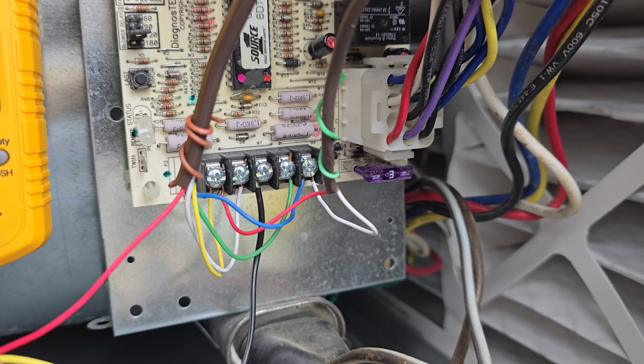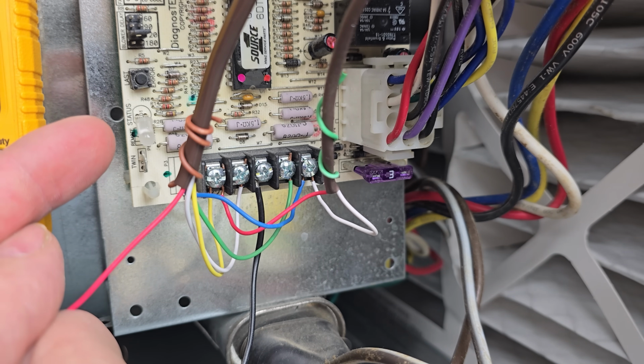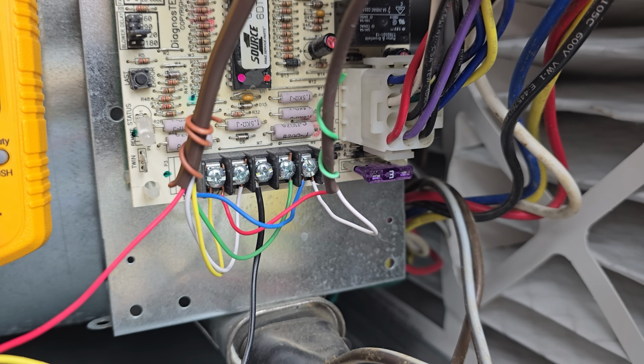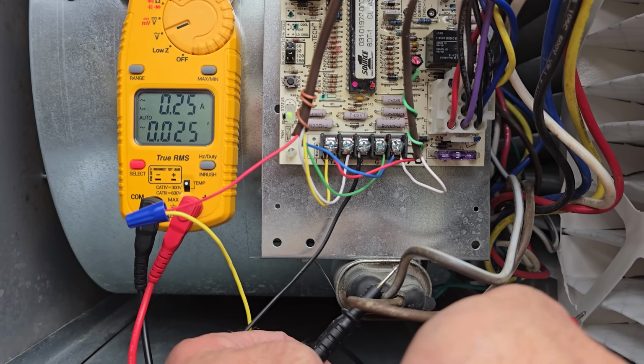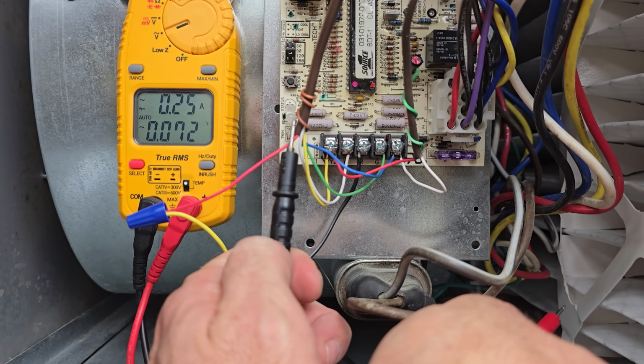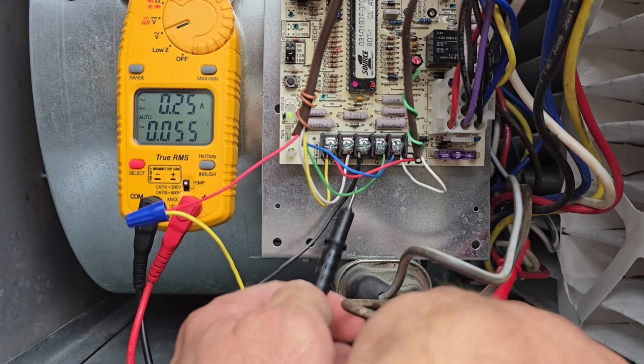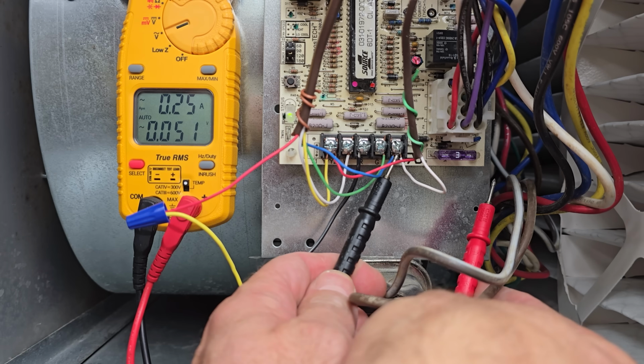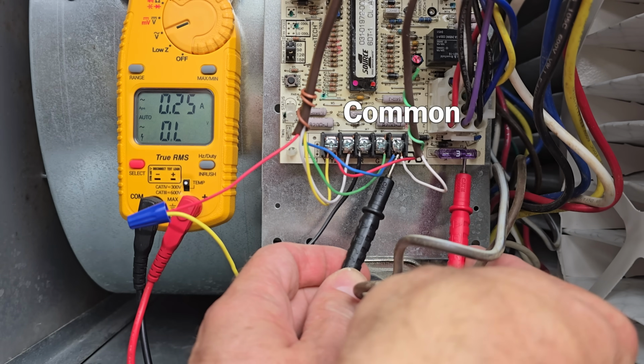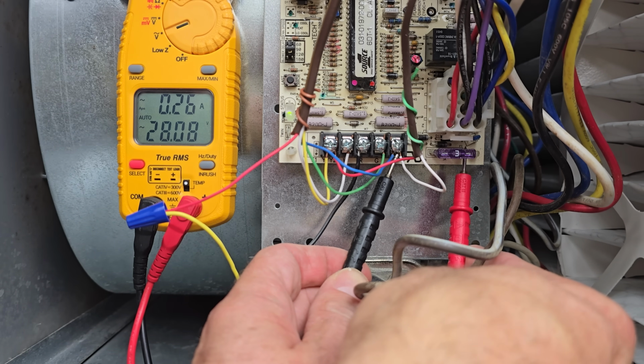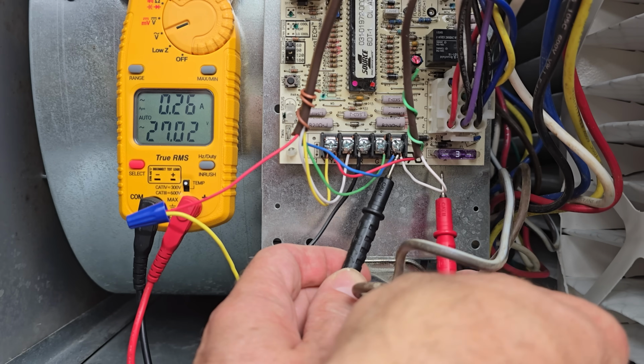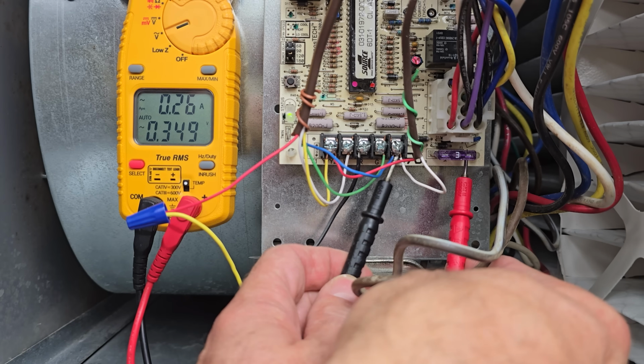So I just put our good fuse back in again, and make sure to replace a 3 amp with the same size. But you see our LED status code light is blinking again. And so if it was not and you had a good fuse, the next thing we want to do is verify that we have power over at that fuse terminal. So say we did not have our status code light being lit, and we did have a good fuse, we would place our probes between our common and the one side of the fuse. We measure 28 volts. That's a potential difference in voltage between, say, this terminal here and this one here.